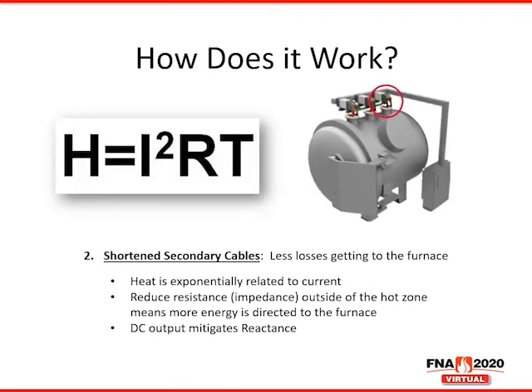On to our second point, our system uses shortened secondary cables. I touched on this on the last slide, but I want to go into the physics of it more in this slide. On the left, you can see Joule's law, which shows heat is exponentially proportional to current and directly proportional to resistance. And by Ohm's law, we know that current and resistance are inversely proportional to each other. So if we can reduce resistance, we can increase the current through the heating elements, which makes heating more efficient. By reducing the length of the secondary cables, we have less losses or less resistance getting to those power feed-throughs.